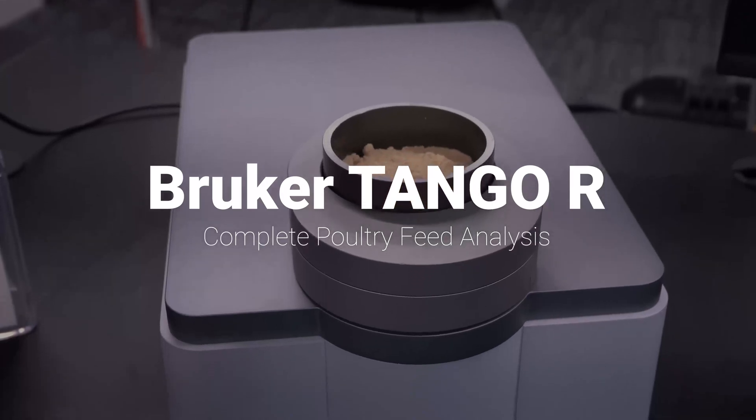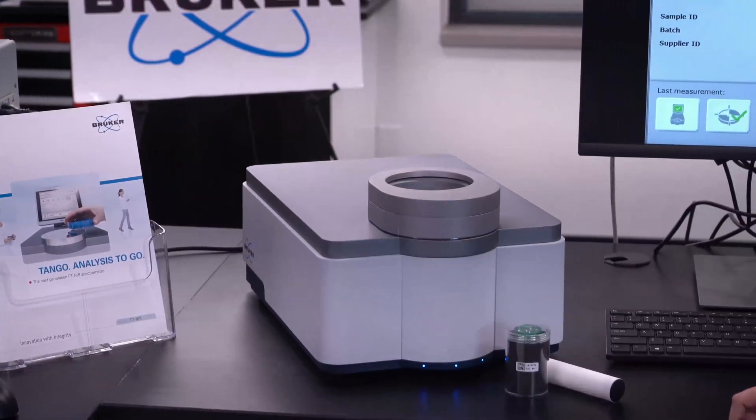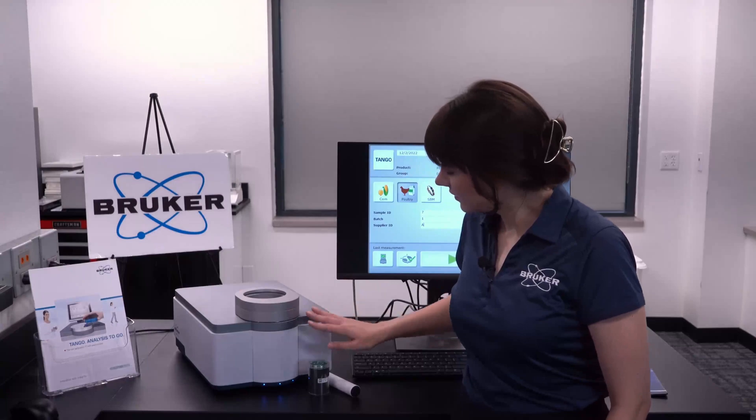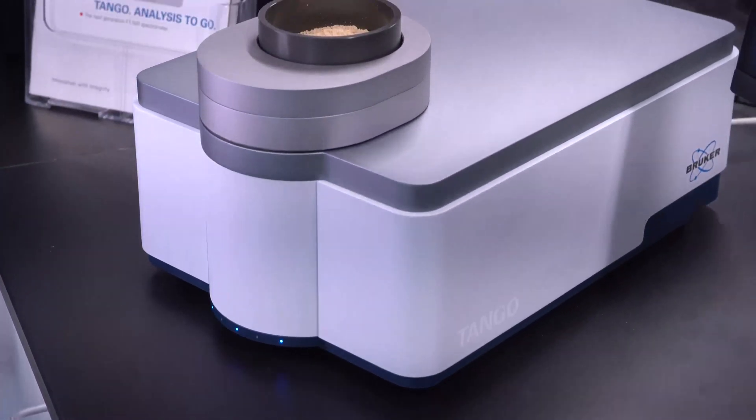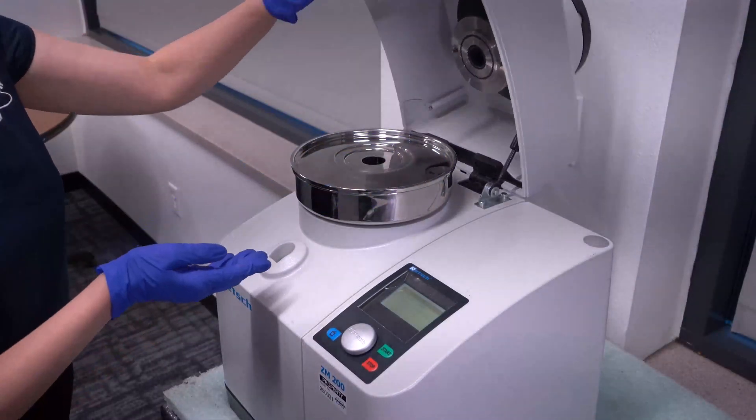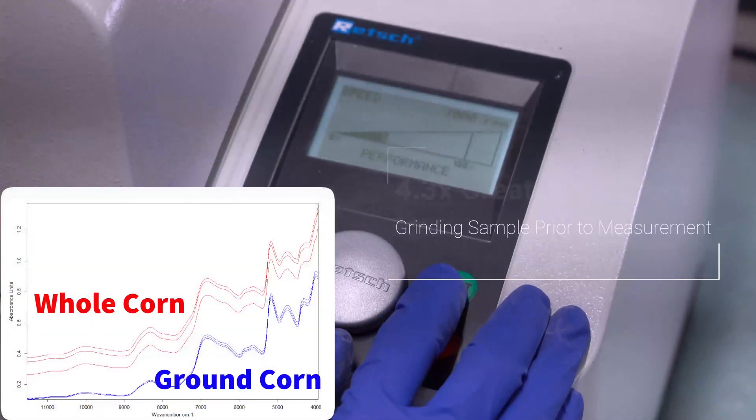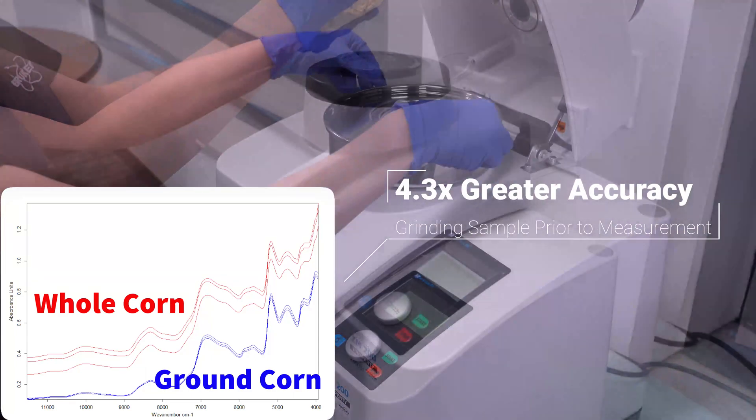Today we're in our Madison lab to address the ever-common question, to grind or not to grind? While the Tango was designed with the agricultural industries in mind, keying in on robustness, a small benchtop footprint, limited consumables and ease of use, accuracy and precision are still of the utmost importance. And we found that grinding samples to uniform particle size will increase both the accuracy of the results and the precision of replicate NIR measurements.